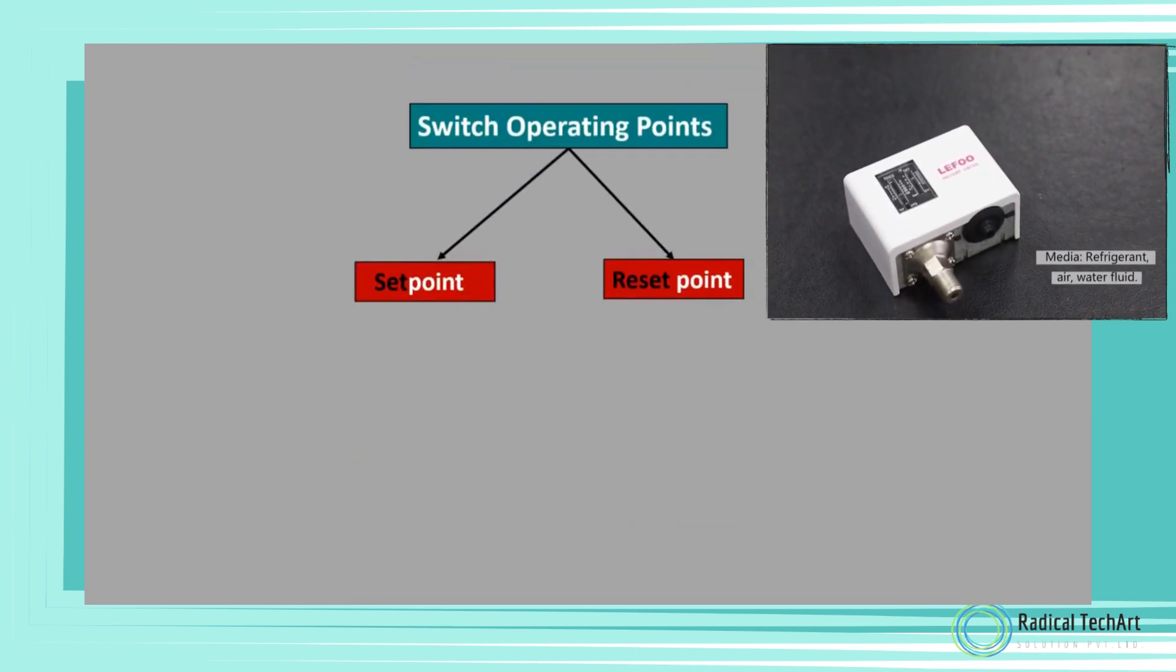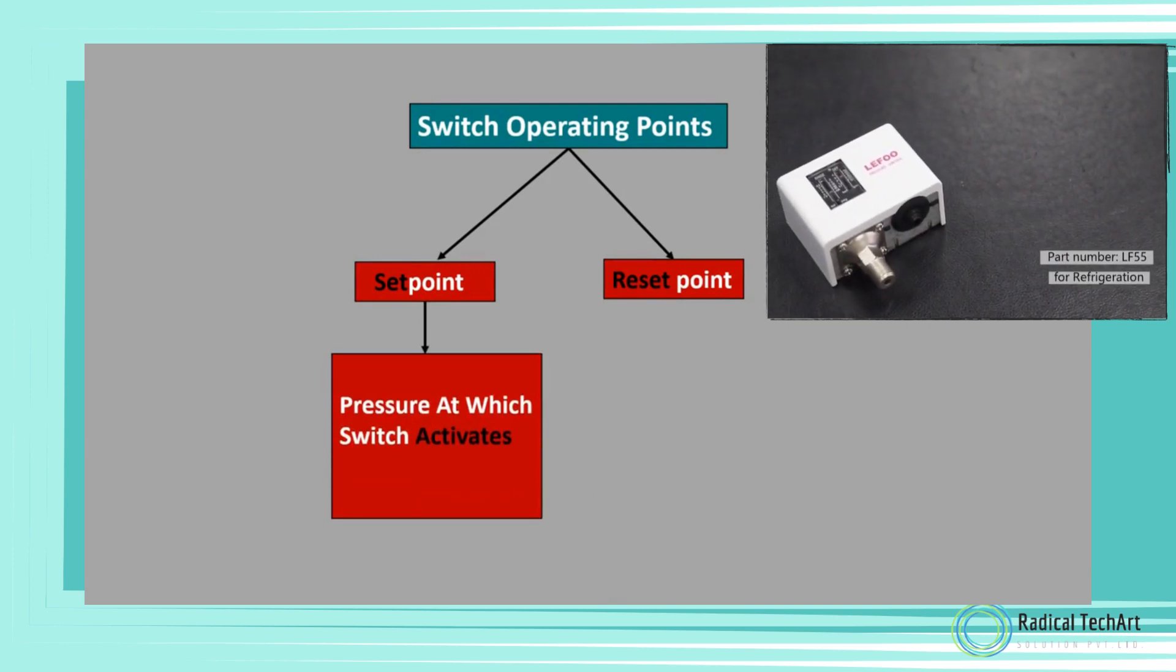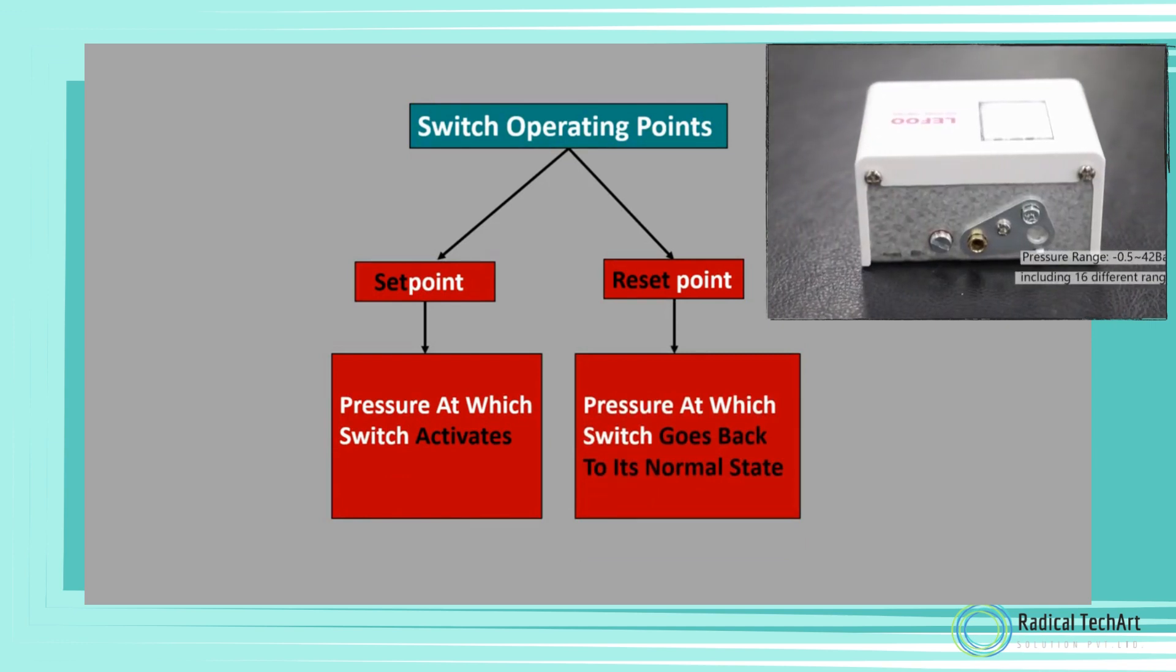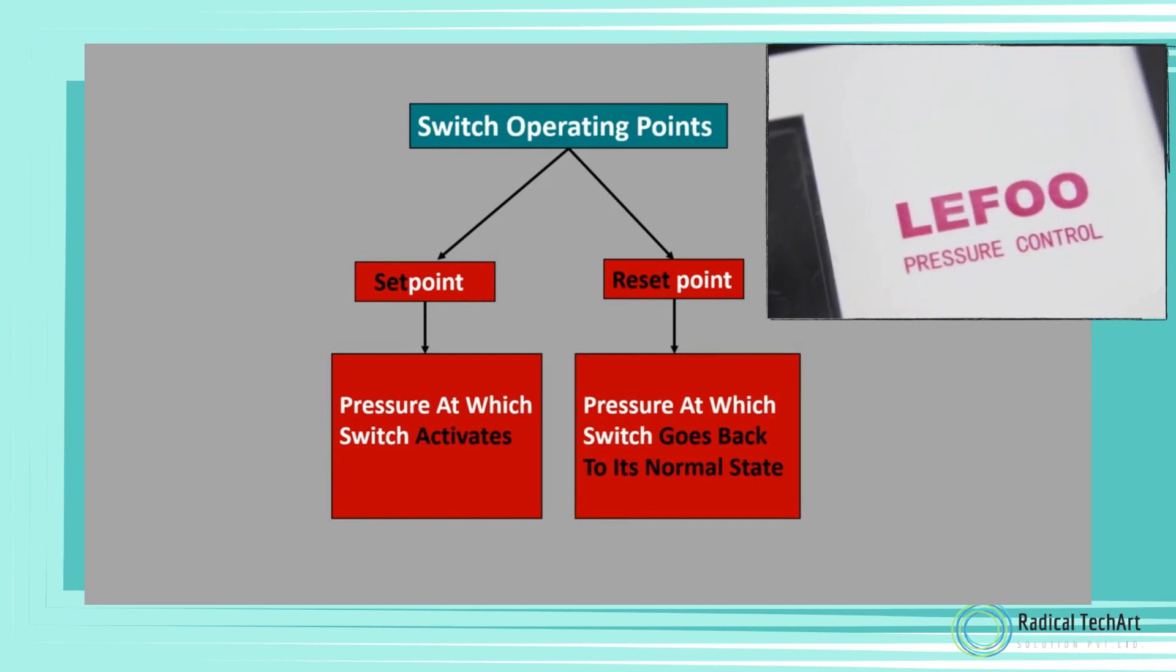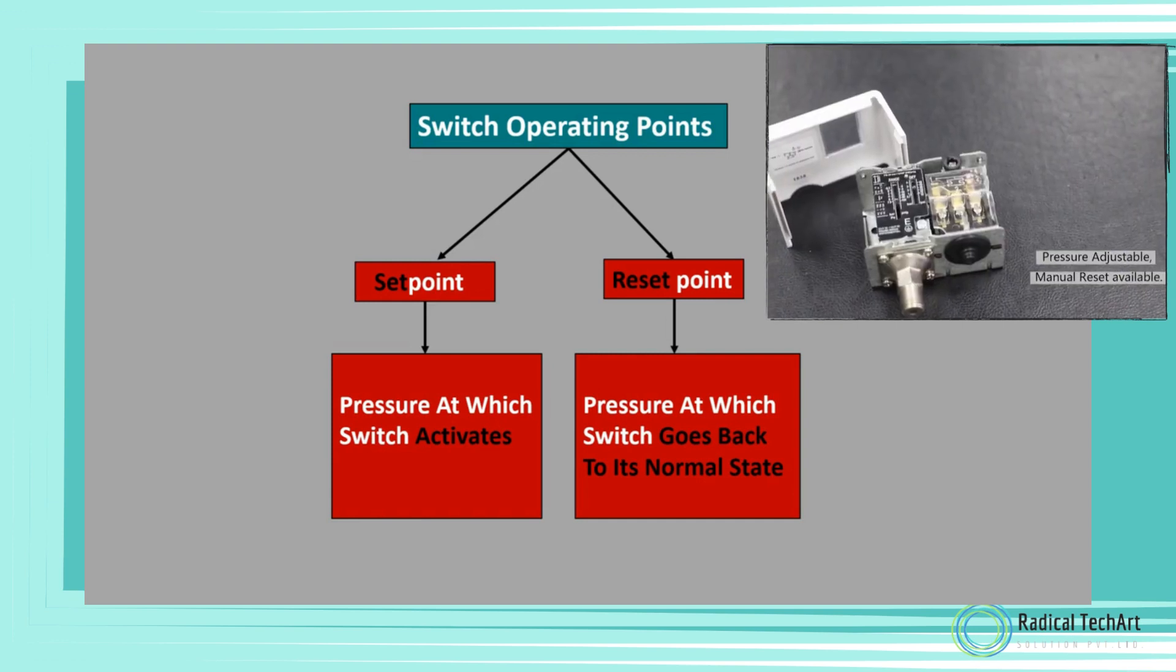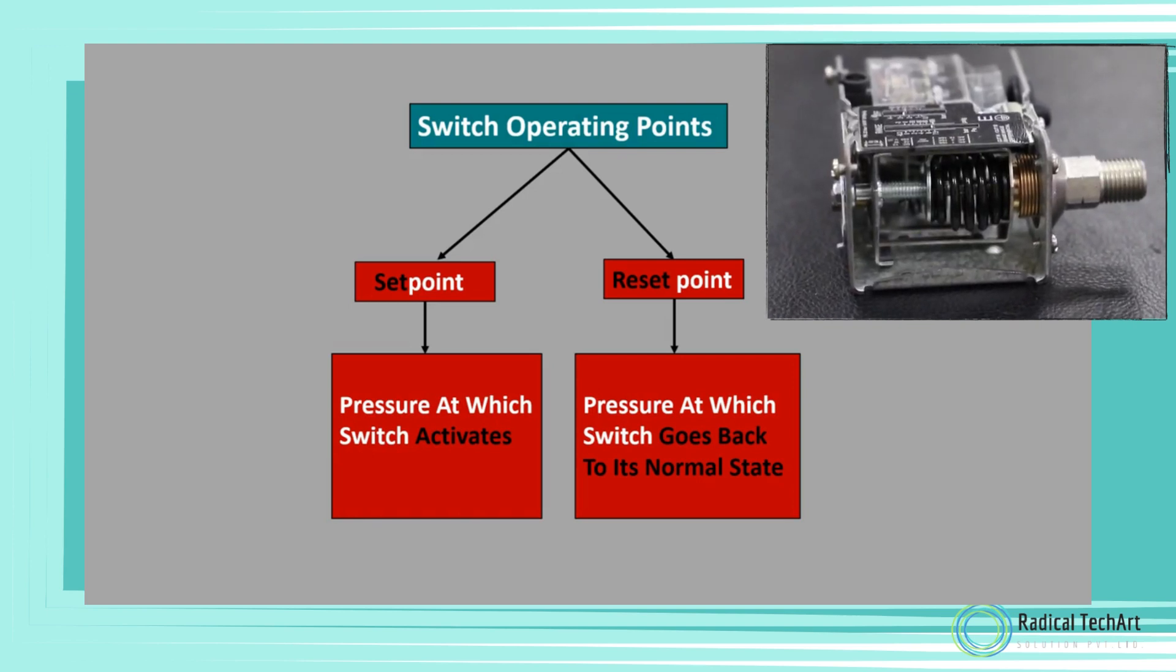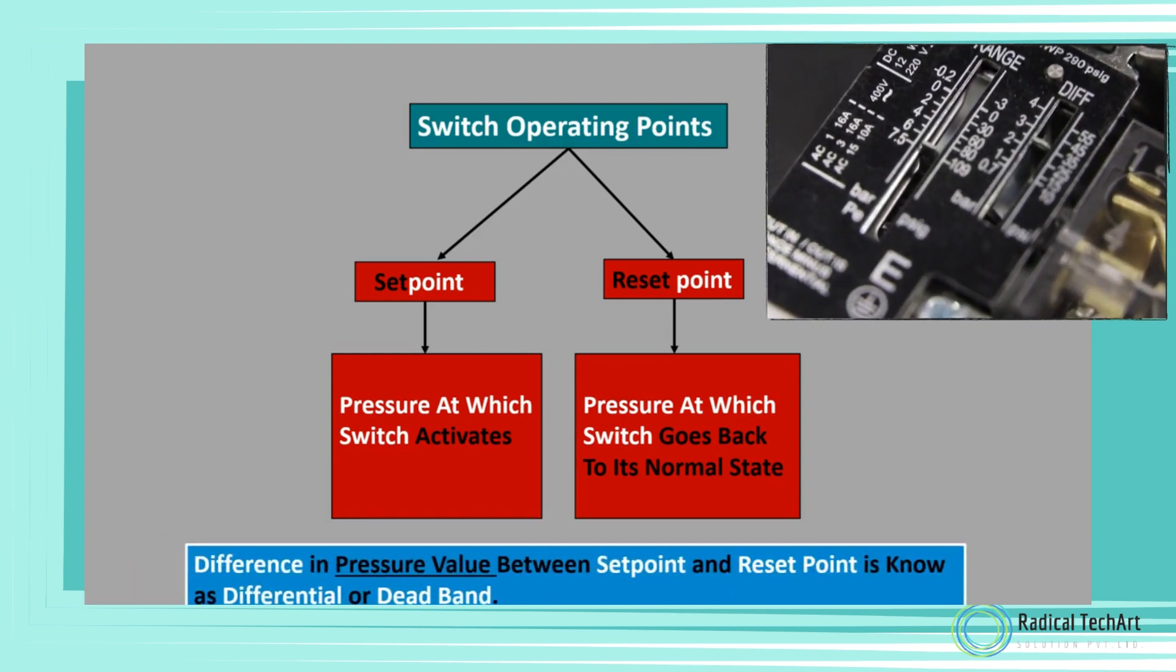All pressure switches have two operating points known as setpoint and resetpoint. Setpoint is the pressure at which the switch activates, and the resetpoint is the pressure at which the switch goes back to its normal position. The variation in pressure does not change the status of the switch until the setpoint is reached. When the setpoint is reached, the switch changes its state from NO to NC or NC to NO and remains in the changed state until the pressure drops below the resetpoint.